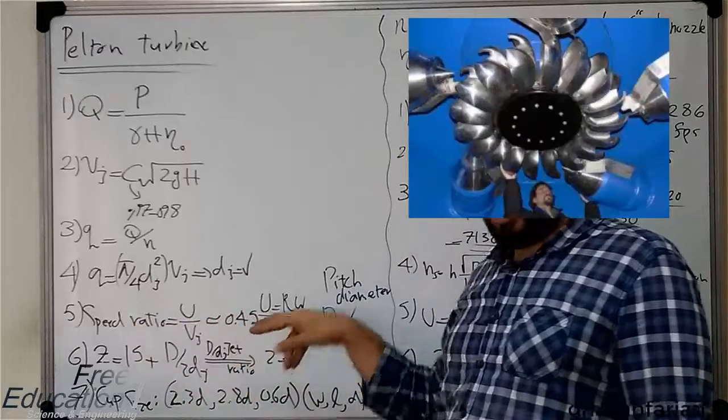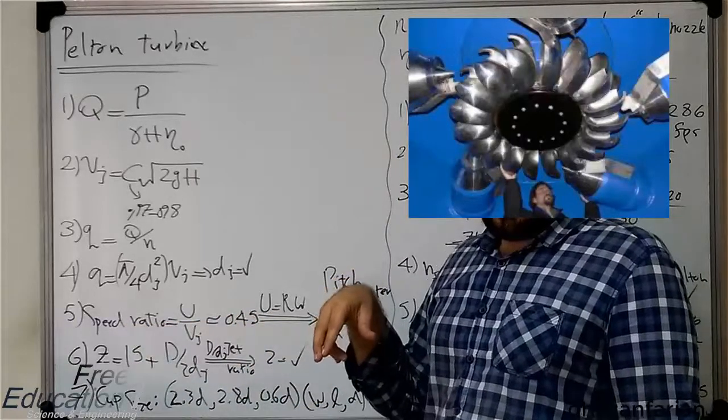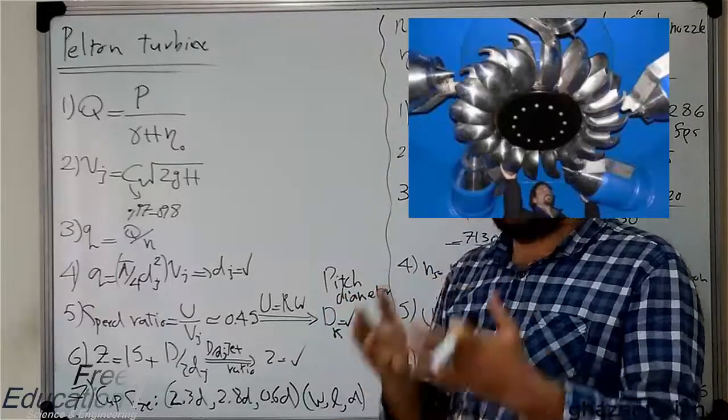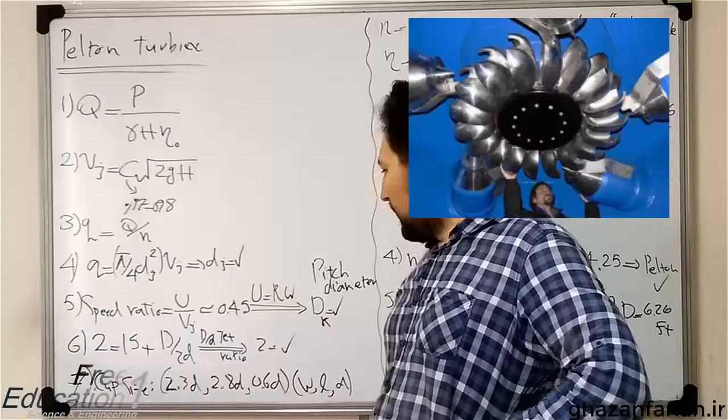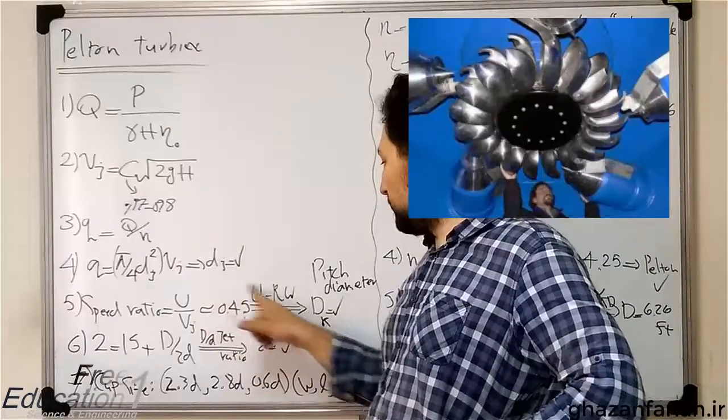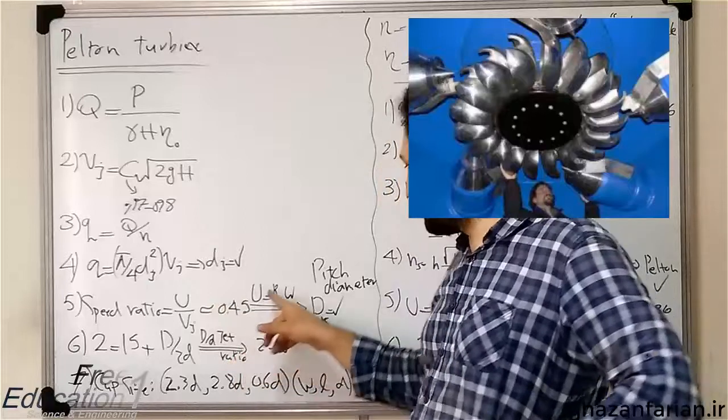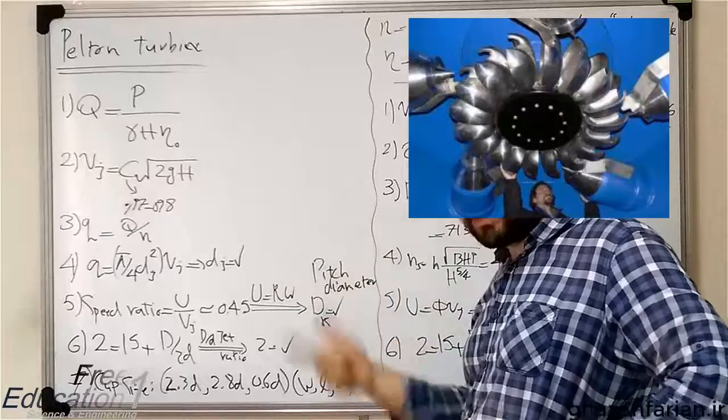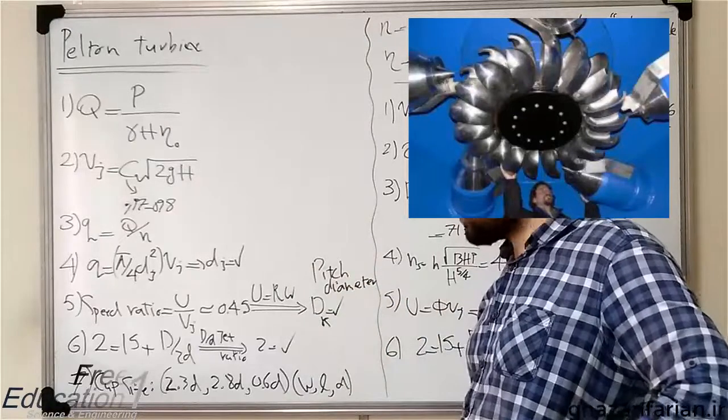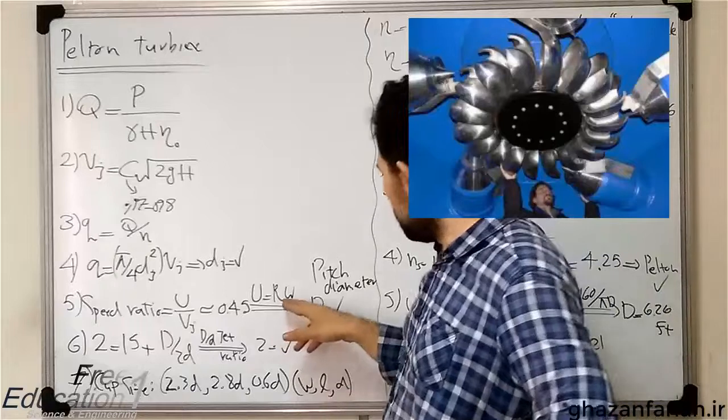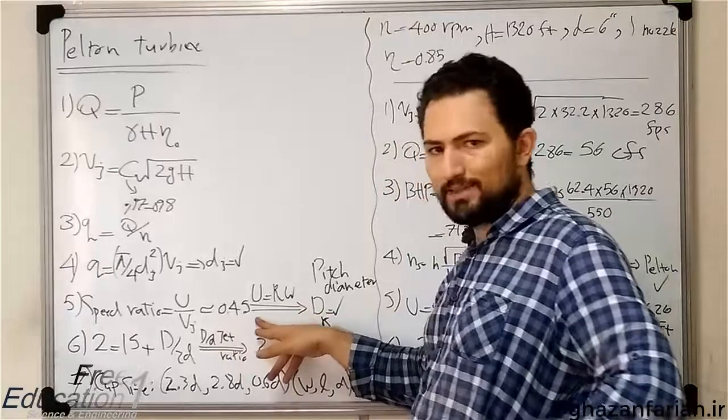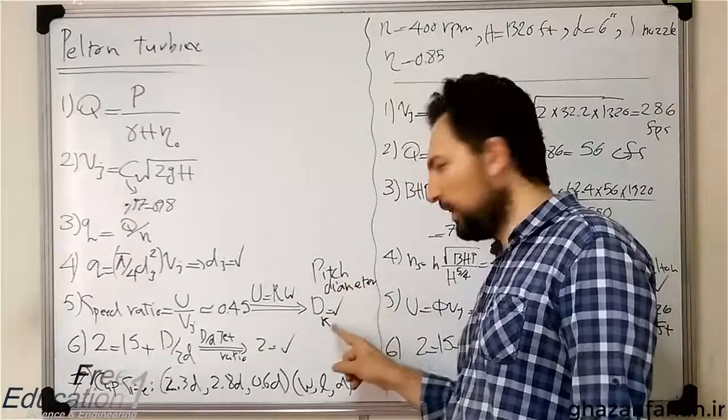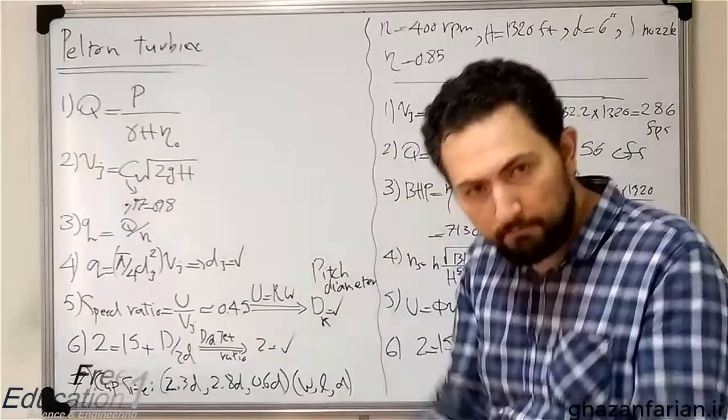So, selecting this speed ratio is similar to the result in the previous session based on the control volume analysis. And this way, using the relation U equals R omega, R is the radius of the runner and omega is the angular velocity of the runner. So, using this constant as an engineering advice, you can easily compute the pitch diameter or the runner diameter or the diameter of the wheel.